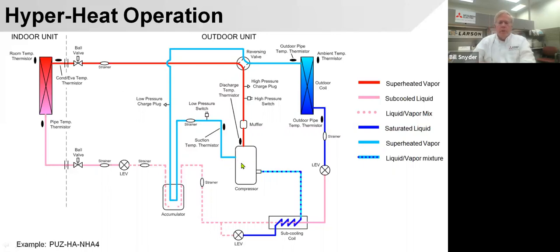Now this is a hyperheat unit, so we're doing some other fancy stuff here. We're trying to capture as much heat off that gas, so we're running through another LEV here, and we're going through a tube-in-tube heat exchanger, and we are cooling this liquid, subcooled liquid, to the outdoor unit, and we have a kind of a liquid vapor mixture that we're injecting into the compressor. So we're injecting some liquid vapor mixture in here. We're ramping that compressor. Remember I said up to maybe as high as 130 Hertz. So that compressor is running really, really super hot and pumping a lot of hot gas into the indoor unit.